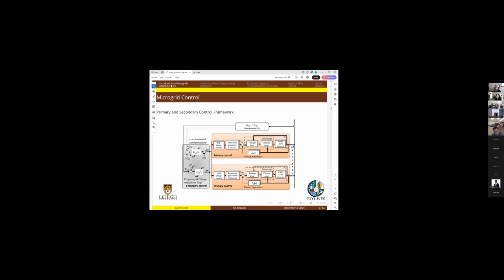Here you see a structure of a microgrid. This is your point of common coupling, and the orange boxes are basically the primary controllers. Here you see two different DERs, but both of them have the same primary control implemented. The first box over here is your inverter, or basically the resource, the DER. And these are the control loops. You have a current control to control the amount of current that is going out of this device, and this is mostly for protection against overcurrents or faults. Then you have the voltage control, which is going to control the voltage at the output of your device. On top of that, you have a controller called the active and reactive, or PQ, controller. Sometimes you hear droop control utilized for this. This is going to control the amount of active and reactive power that you're sending out from this device. So this is the structure of the primary control.